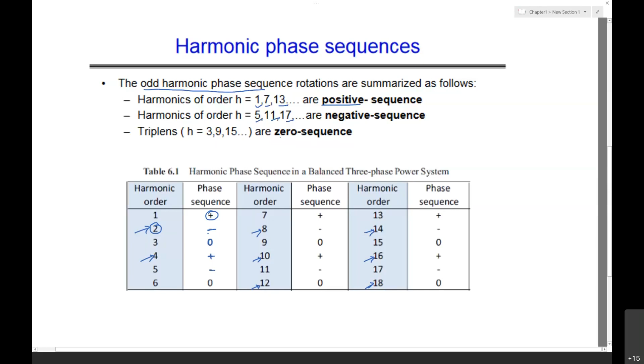This is about the harmonic order and how it represents the sequence component. The even harmonics will not be present in our system. The second and then the fourth and then the 8th and 10th harmonics won't be there because of the half wave symmetry. These harmonics will not exist in an electrical system. So they have represented only the odd harmonic phase sequence: the harmonic order of 1 is of the positive sequence, then 7th and then 13th. The negative sequence components are 5th, 11th, 17th. All the triplen harmonics will be existing. These triplen harmonics represent a zero sequence.